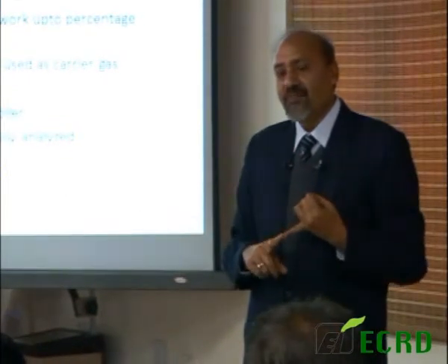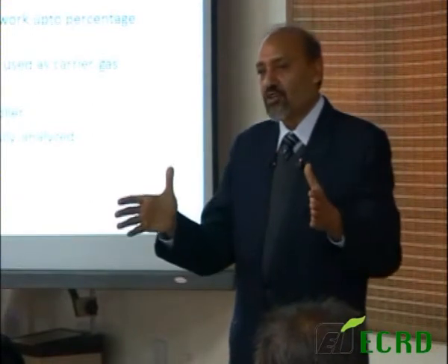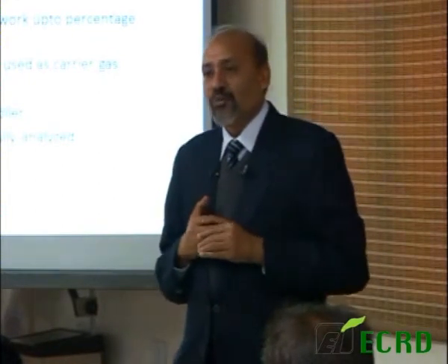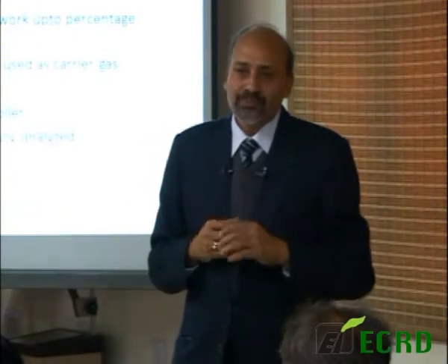So basically they've integrated 3 things: an air sampler, desorber system, a GC and a PC, all inside one box. Makes a very nice, neat assembly. They've also done things like automating the calibration system, linearity checks. So all of those things have been very nicely integrated into a standalone machine.